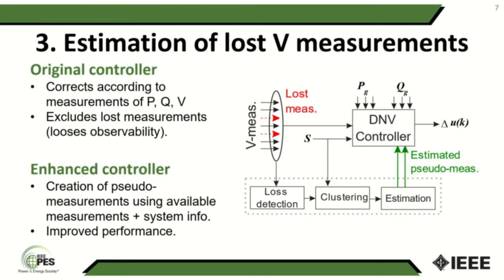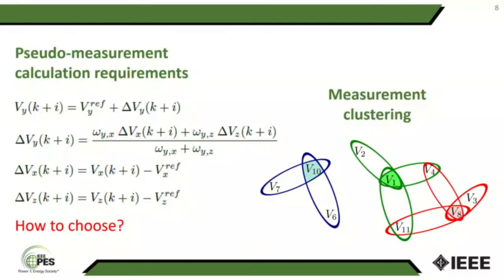There are three stages for the estimation process. The first one is the detection of the loss. The second one is a clustering phase to select the most suitable measurements to estimate the lost one. And the third one is the estimation itself. In summary, the pseudo measurements are built based on the last measured sample, that we call Vref, plus a term of voltage evolution, with a delta, as a weighted sum of the evolution of two candidate buses, or available measurements.